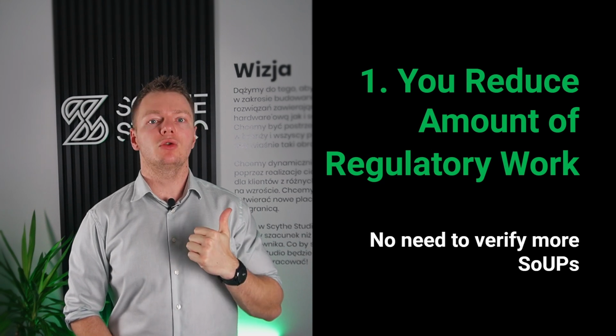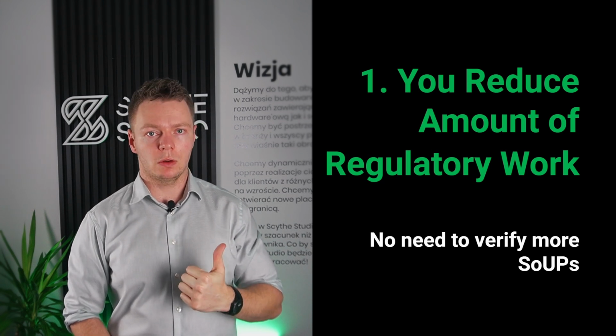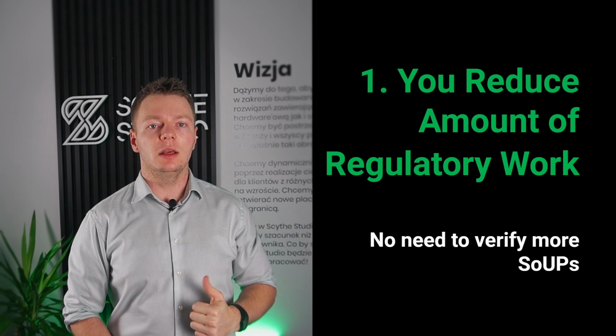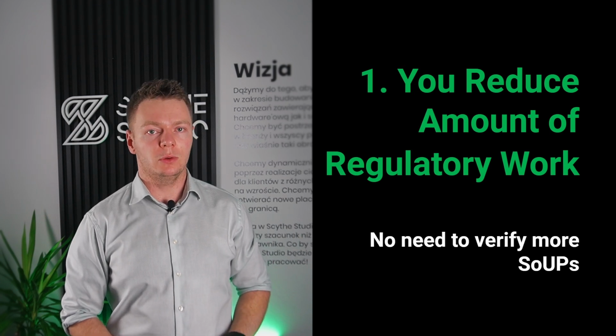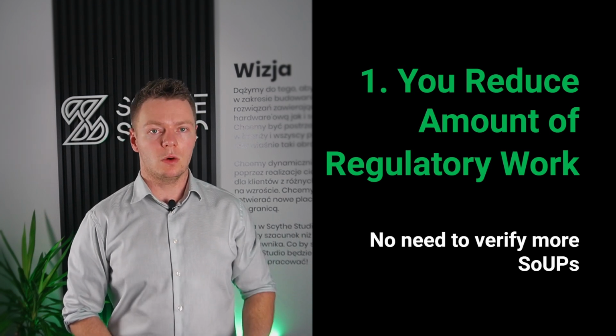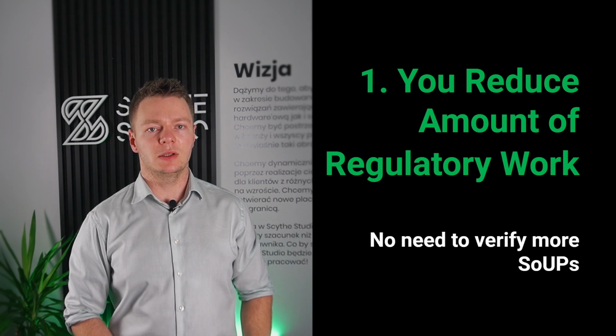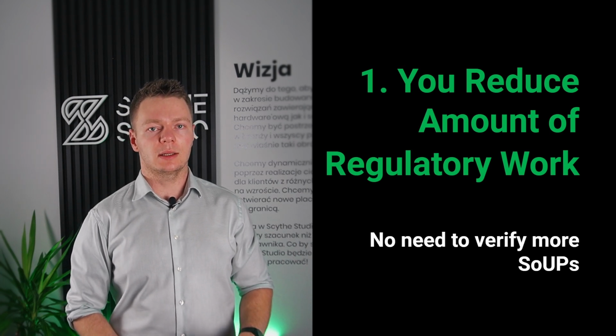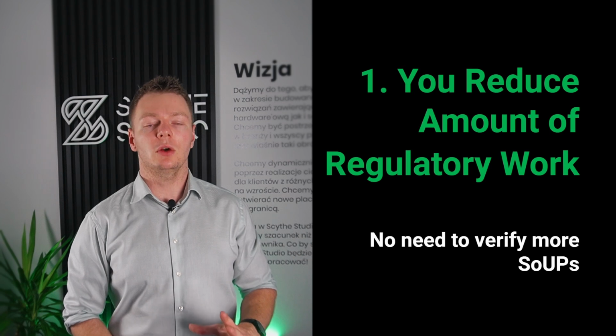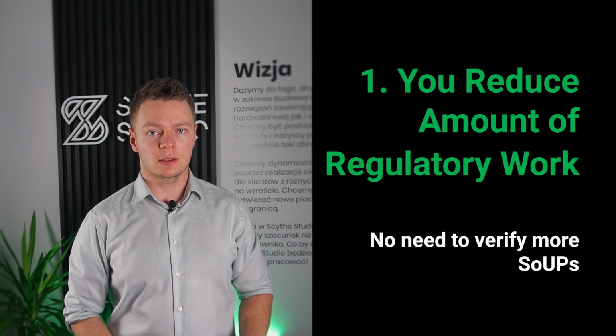First, it reduces the amount of regulatory work. In the reality of medical software, you have to document a lot. All frameworks, libraries, dependencies should be documented as SOUP, software of unknown provenance. The less you have, the less you have to verify and less to describe in your paperwork.